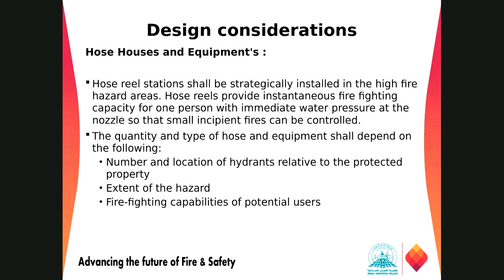A minimum clear space of 15 feet is required in front of every hose reel. So if this is our fire hose cabinet, in the front side we should have at least 15 feet of clear space to lay down our hose and fight the fire in those areas.